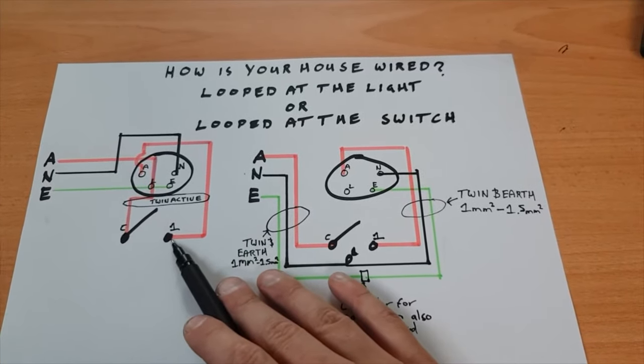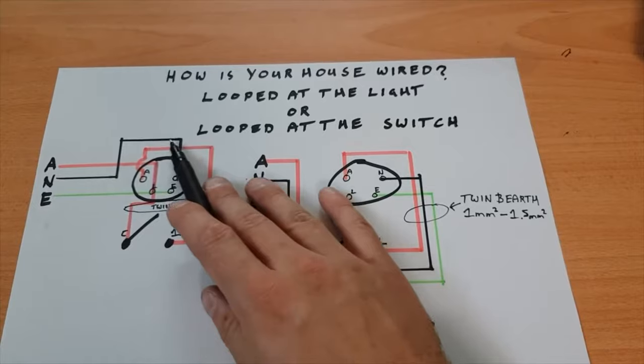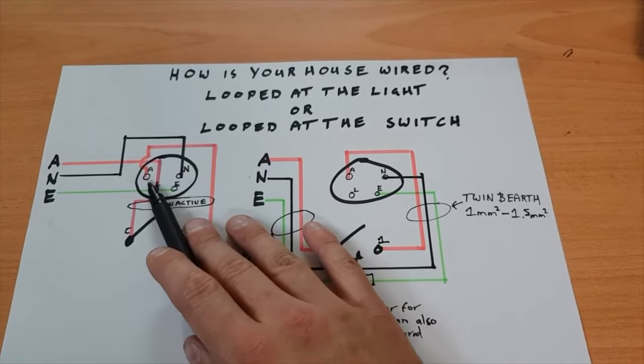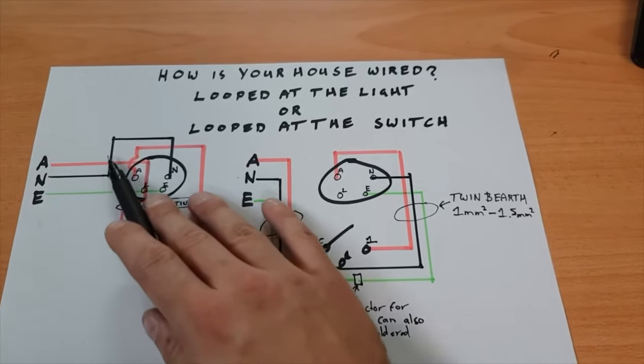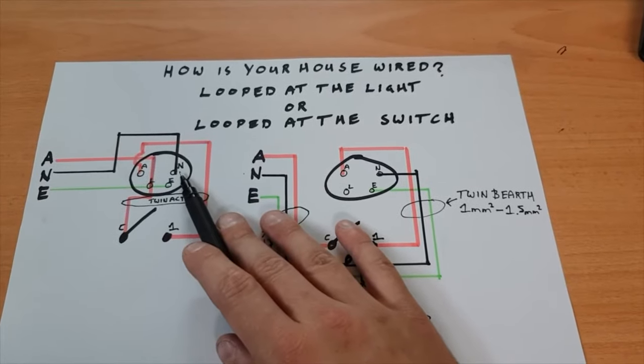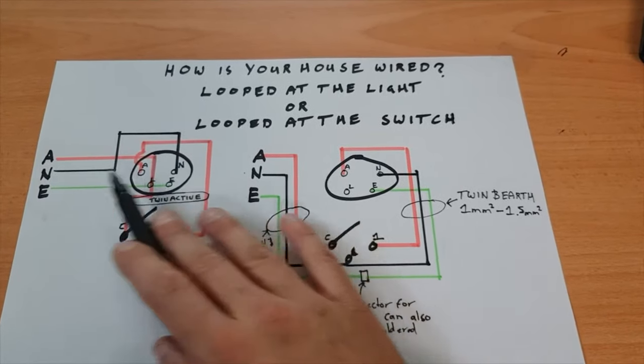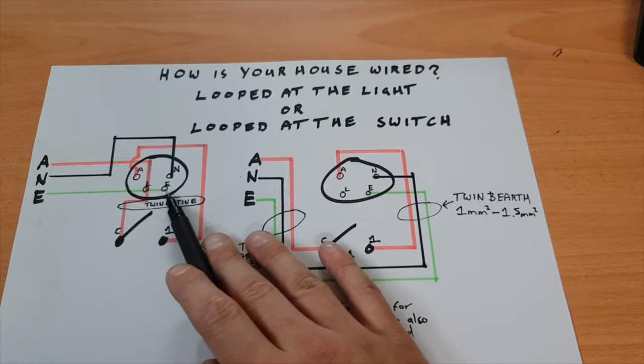Once that is flicked, this bar here, once that flicks down, the power will flow through the switch back up to the light active. Then basically your neutral just goes straight to your neutral terminal of your light, and then your earth goes straight to the earth terminal of the light.